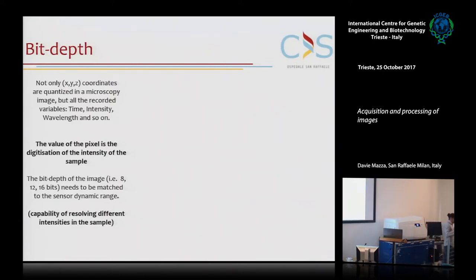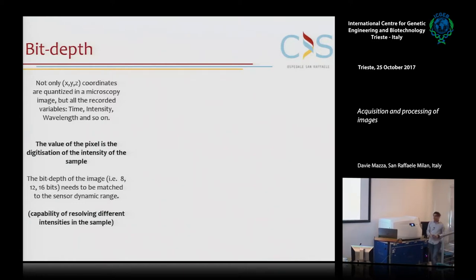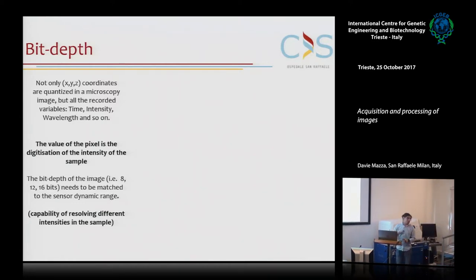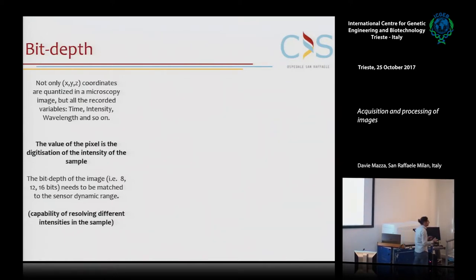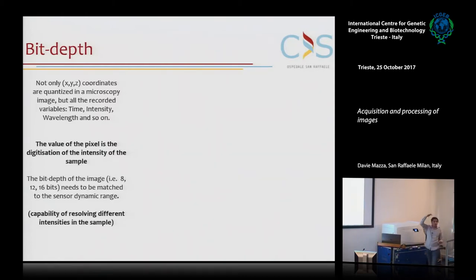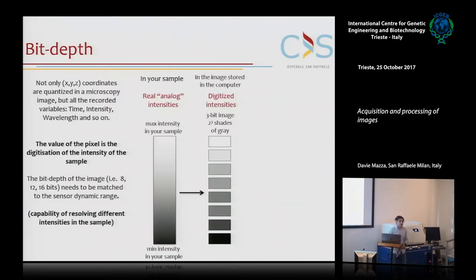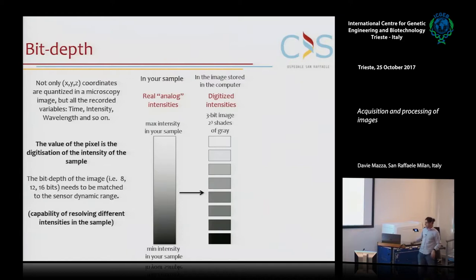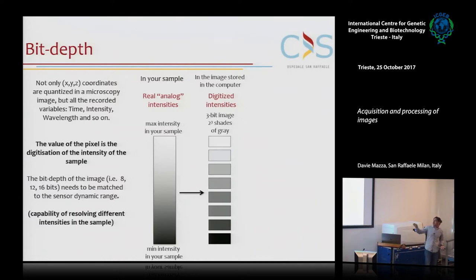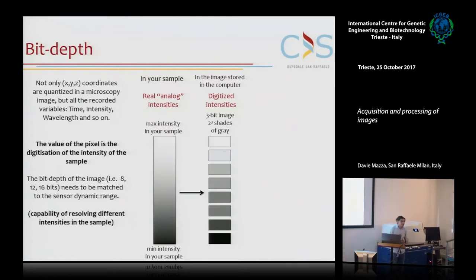Not only is position in space digitized in the pixel, but also intensities. Another concept to introduce is bit depth - the number of gray values in which we divide the intensity in our image. Your sample has a continuum of intensities, but you generate an image that is digitized to a certain number of gray values. You can choose how many gray values you want, which is usually the number of bits with which you acquire your image - typically 8 bits or 16 bits.